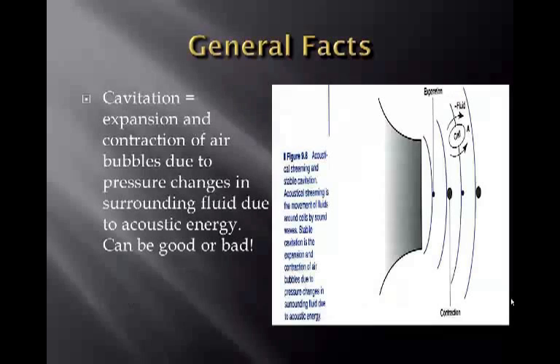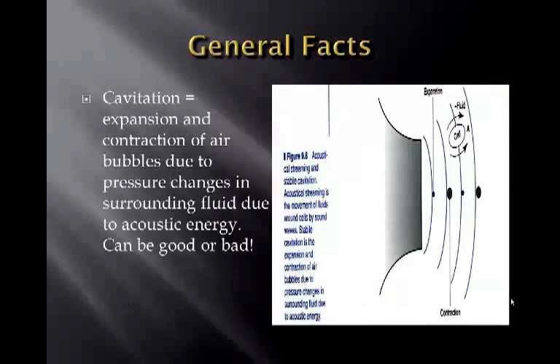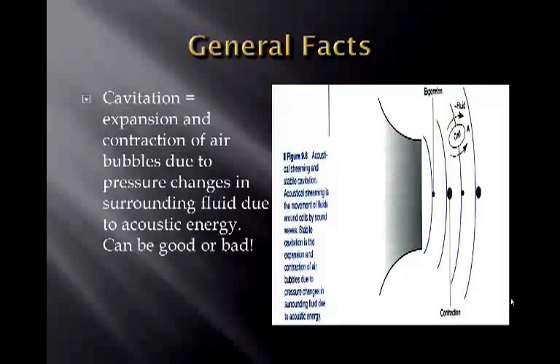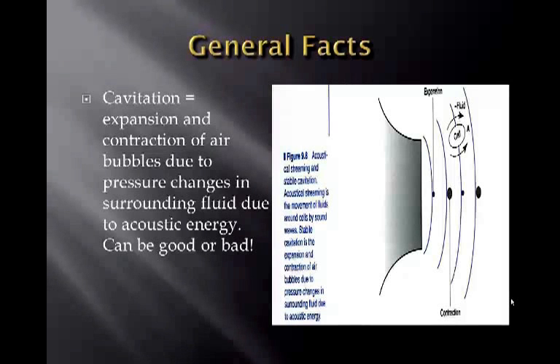Cavitation is the expansion and contraction of air bubbles due to pressure changes in surrounding fluid due to acoustic energy. This can be good or bad, so you want to have stable cavitation when you're selecting settings for your ultrasound.